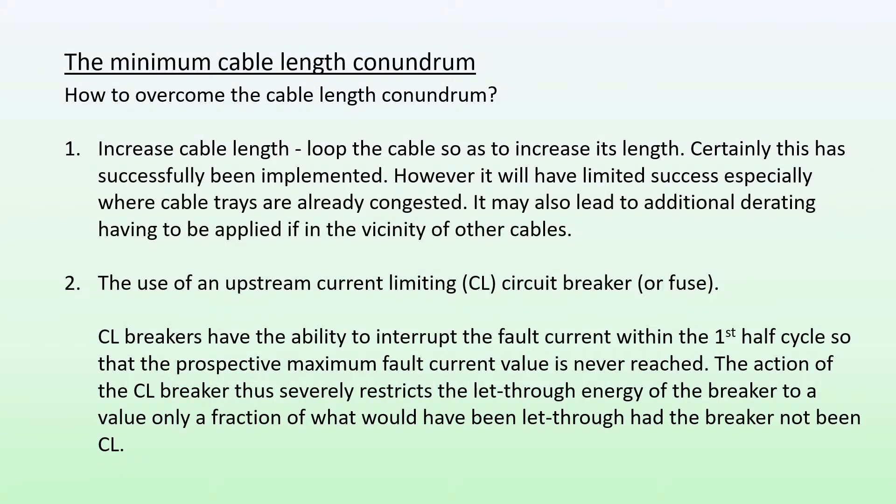So how to overcome the cable length conundrum? Well, one possible solution is to increase the cable length—the cable may be looped. This of course will increase its length, and certainly this has been applied in the past successfully in many instances. However, it will have limited success, especially where cable trays are already congested. Also, it may lead to additional derating factors having to be applied if the cable being looped is in the vicinity of other cables.